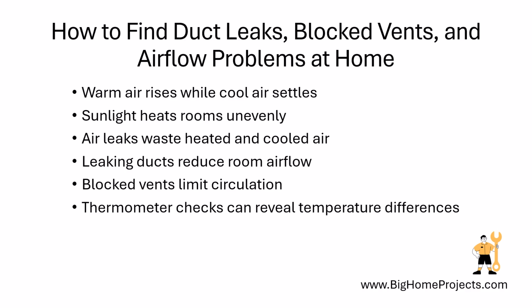Dirty filters and clogged indoor coils can also weaken the entire air system, even if the thermostat says everything is working. To find the cause, close all windows and doors, replace a dirty filter, make sure vents are open and uncovered, and hold a tissue near duct connections to look for moving air. You can also compare room temperatures with a simple thermometer and ask a contractor to inspect insulation, ductwork, and air leaks instead of immediately replacing the entire system.